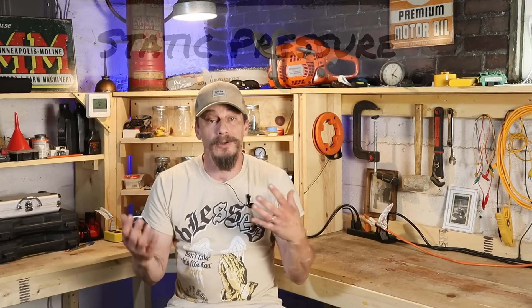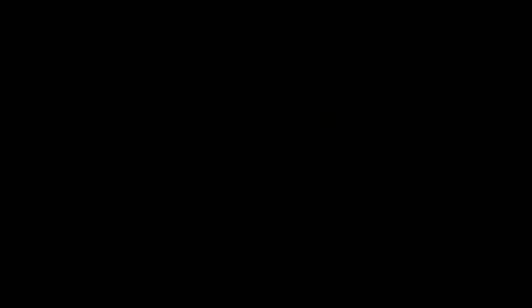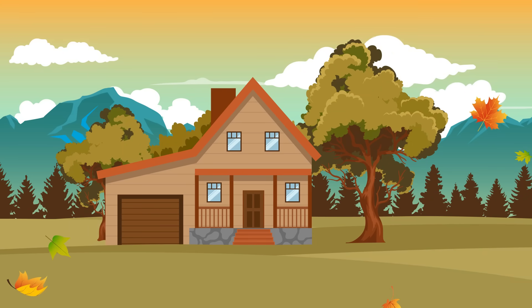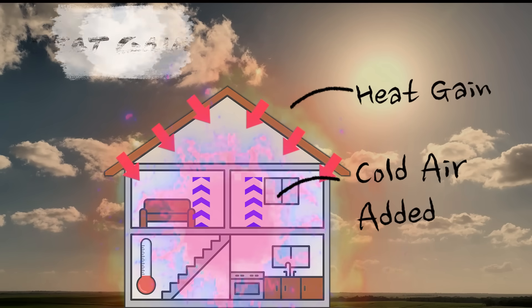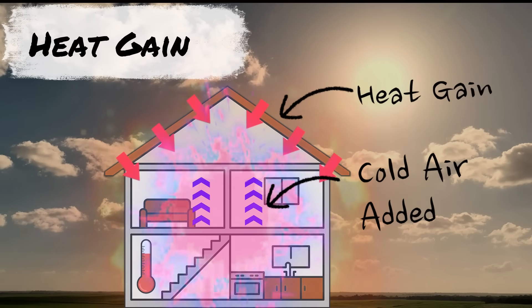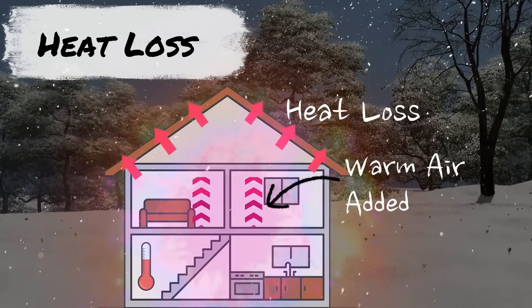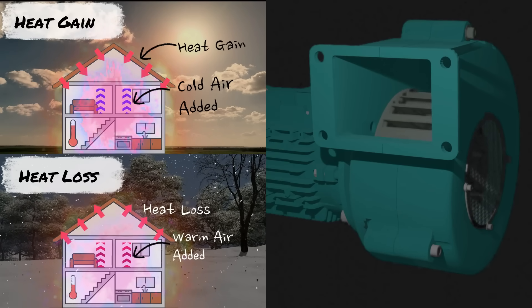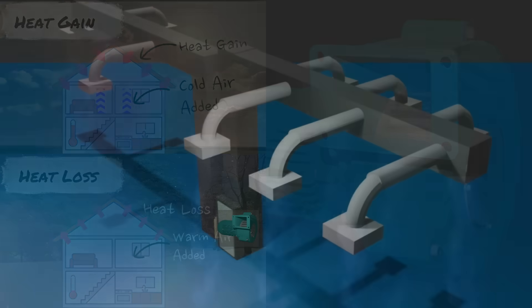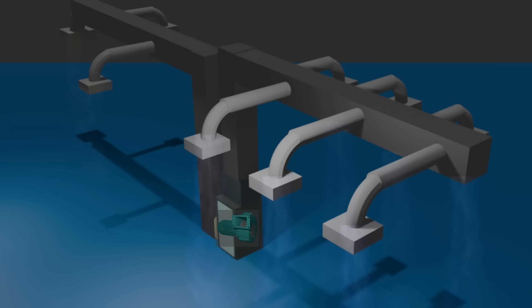You may be wondering how this one number can tie into all those things. We're going to start with why static pressure plays such a big role in all these different facets of a system. Whenever we try to heat or cool a home, we're actually fighting against the amount of heat that the home naturally gains or loses while we're trying to condition the air. Static pressure is the resistance that pushes back against the blower's effort to deliver the required volume of air that we need.